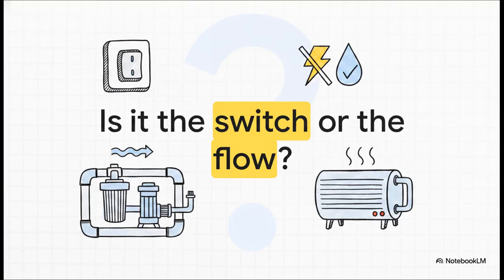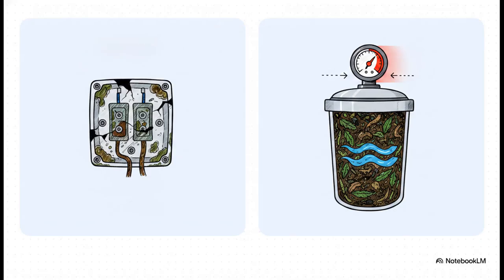So the very first safety gate the power hits is the pressure switch. Because this checks for water flow, it accounts for the vast majority of our cold pool problems. When this switch fails to let power through, we have to pause and ask ourselves the golden troubleshooting question: is the switch itself broken, or is it actually doing its job perfectly? See, a true switch fault means broken hardware, maybe corroded terminals or a bad internal diaphragm.